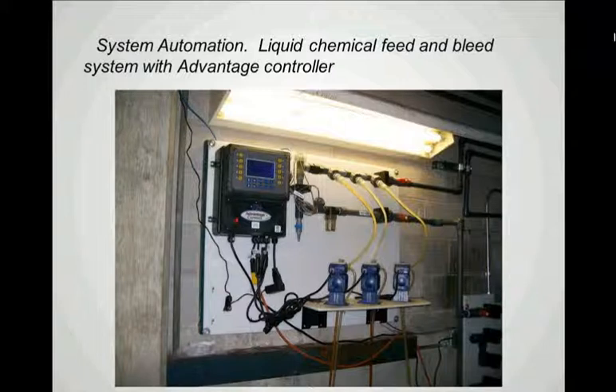But here we see a PLC-based controller, and we have a flow of water that comes from the cooling condenser water circuit. It flows through and over sensing probes in that loop to measure the conductivity. And then here we see chemical injection points in that loop so that we can feed the appropriate scale and corrosion inhibitors into the system.